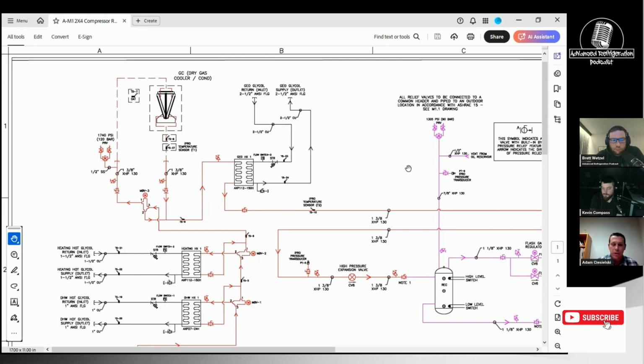Industrial systems that are built for 90 bar, you can raise that pressure and temperature, and it works very well. You can push in and out, very similar to a typical HFC system, where you can complete the entire defrost in 10 to 15 minutes with drip time, everything. So you might be in active defrost for 5 to 8 minutes and you defrost a coil. So it works very effectively.